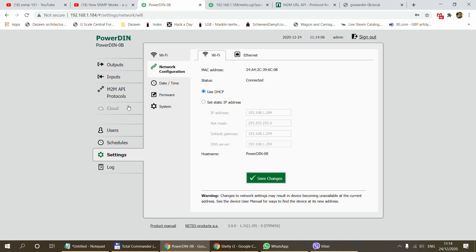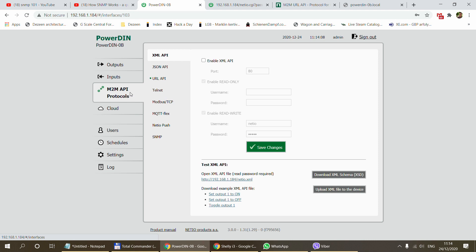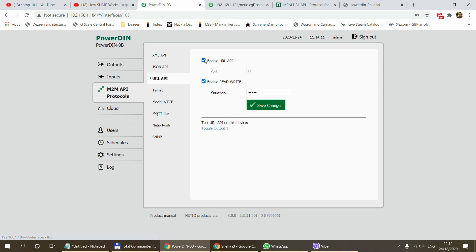The next thing we need to do is go to the M2M API protocols. Because we are going to use the URL API, you just have to enable that. You have a couple of options: you can specify the port — I just left it on port 80 — and you can enable read and write, which we definitely want to do because we want to control the outputs. You can also specify a password, which needs to be included in the URL.